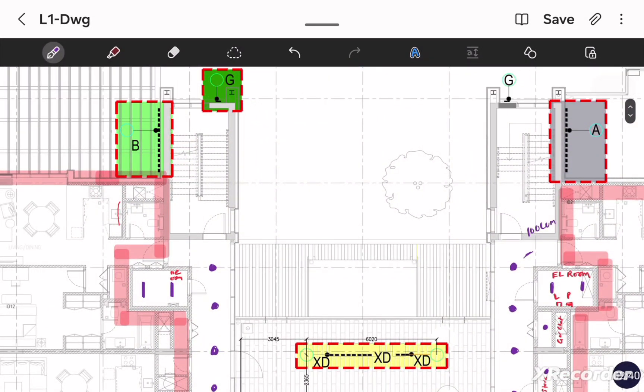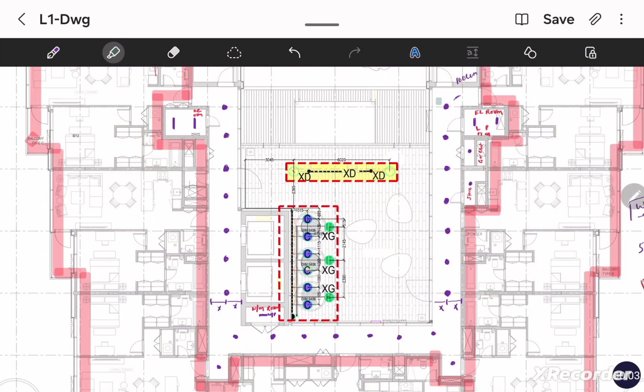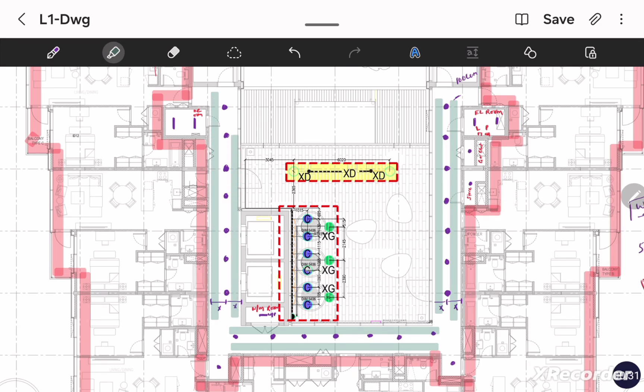The staircase will not be covered on the first floor because the staircase light will be fed from the ground floor DB. Now we have distributed the lights in the corridor and the service rooms. Apart from that, we have bulkhead hidden lights. We will distribute the bulkhead hidden lights on both sides of all corridors. So we have now 100% completed the light load distribution inside the common area.